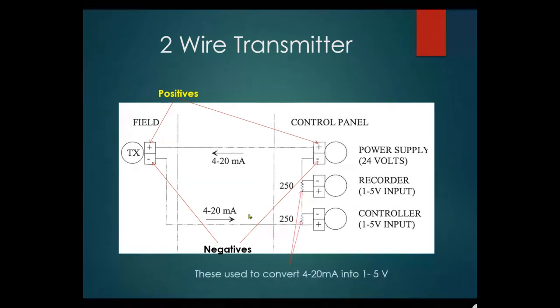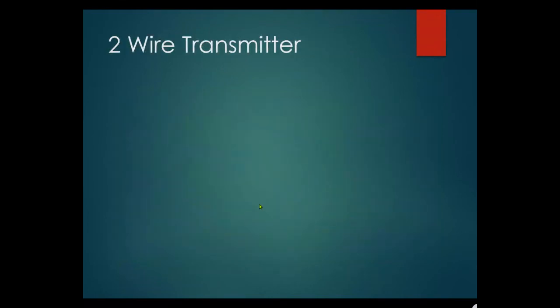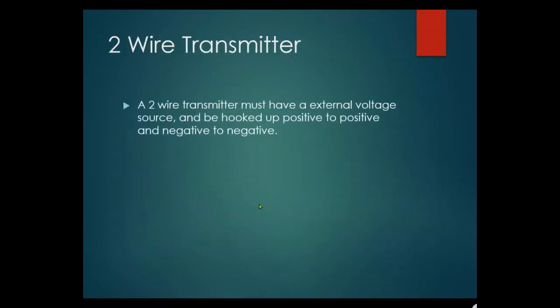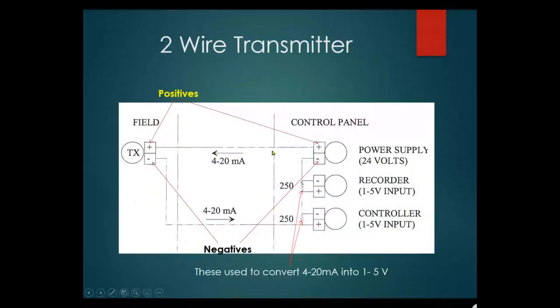Two-wire transmitters must have an external voltage source and be hooked positive-to-positive and negative-to-negative throughout the loop. Going through the devices you go positive to negative, then negative to positive, then positive to negative — and the negatives meet up at the end of the loop. The 250 ohm resistors provide the 1 to 5 volt signal conversion.